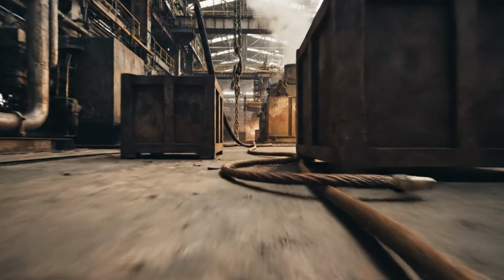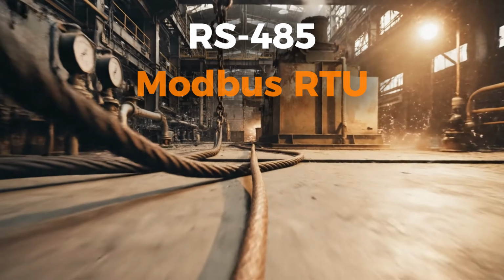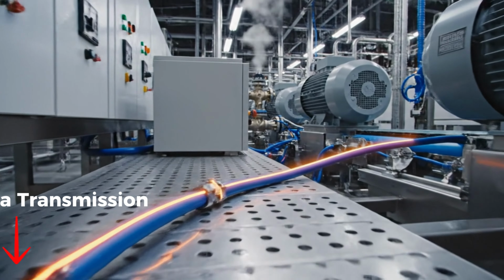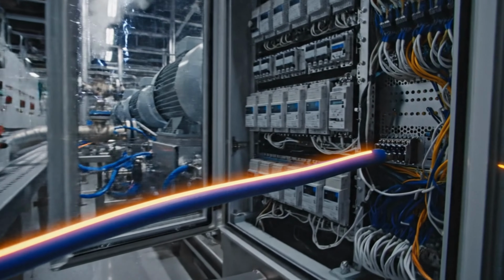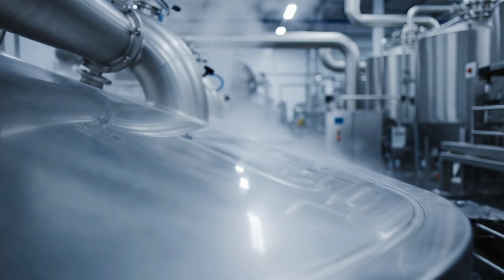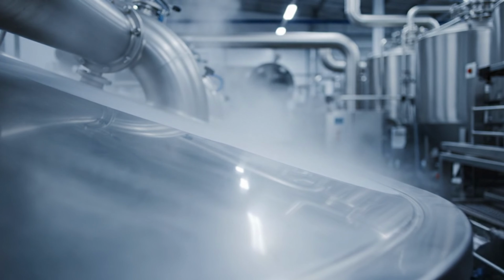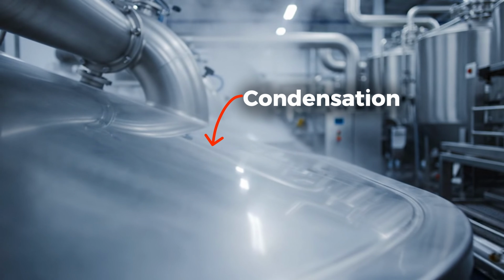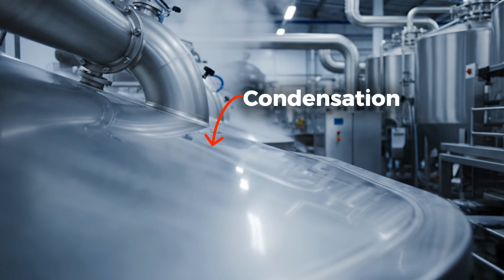Communication is handled over RS-485 using Modbus RTU, providing reliable data transmission over long distances and electrically noisy environments. Dew point is calculated in real time, allowing early identification of condensation risk before moisture forms on surfaces.